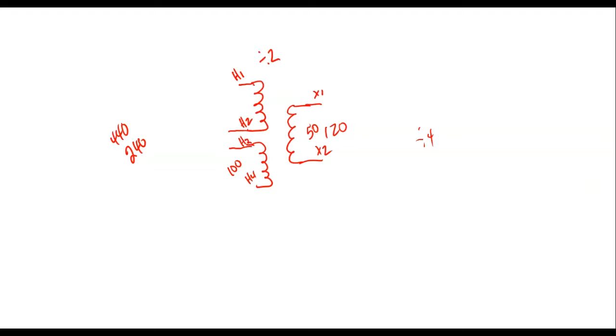Now, if I wanted to hook it up for low voltage on the primary, that means the primary current has to be bigger because the voltage is going down. So what we do is come up and hook them in parallel, so each coil shares half of the current.